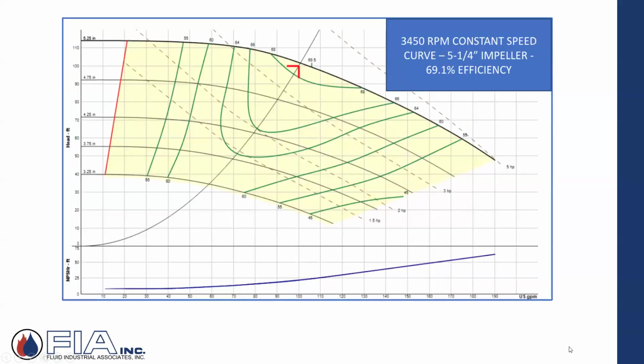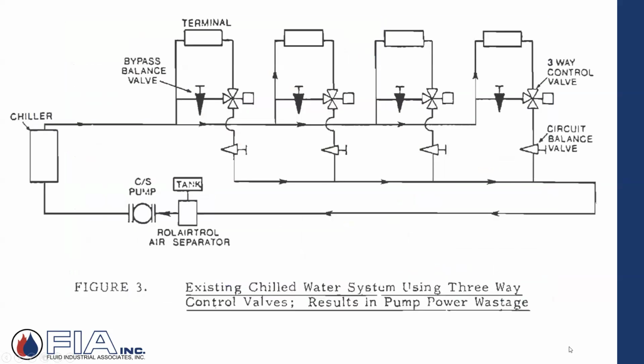So that's what would happen as you backed up on the curve, because that pump has to operate somewhere on that stated 5 1/4-inch impeller diameter. Why? Because you designed it, you selected it for this set of conditions, 100 at 100. When you have the part load, you're moving. Not variable, it's fixed. This is what happens in the system.